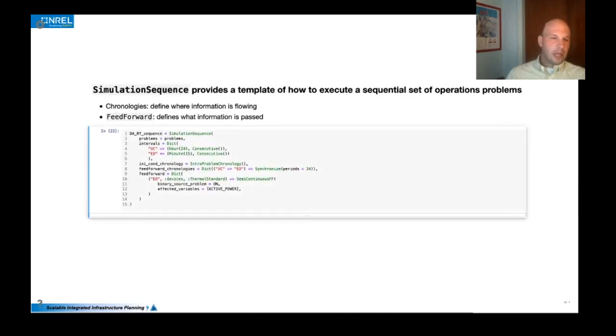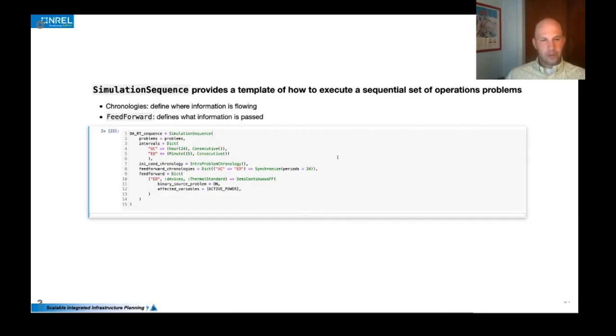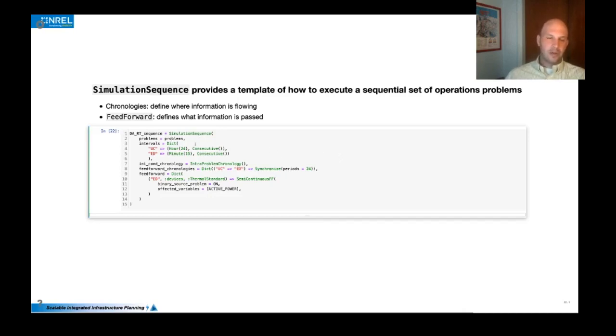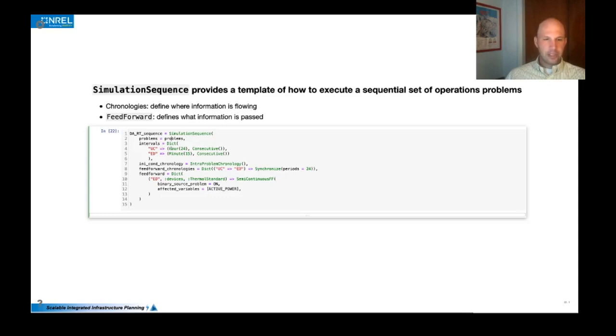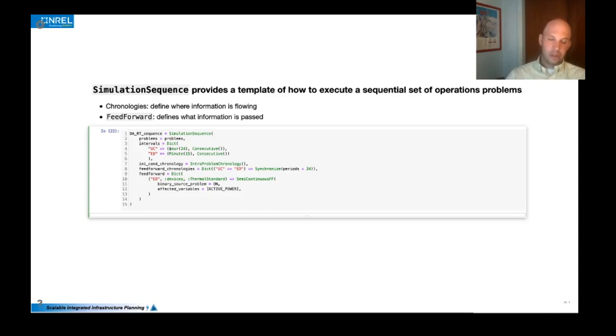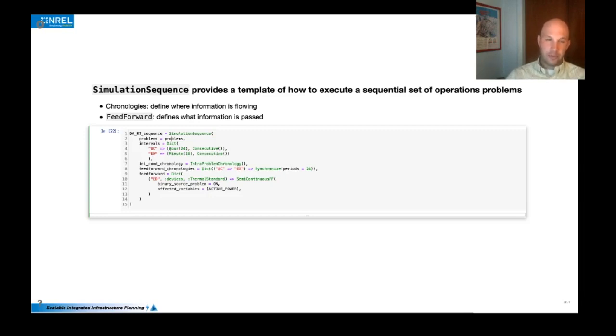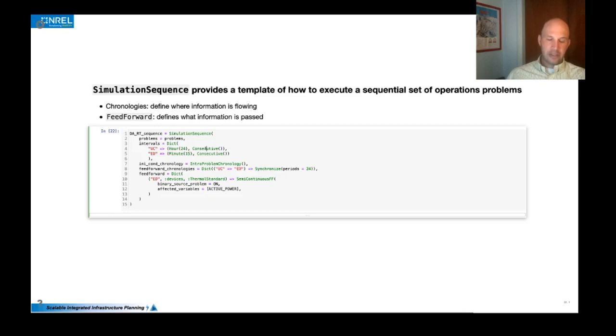And then finally we can also define the way that information flows between those problems and between different steps of those problems. And so we call this a sequence and the sequence really takes that list of problems and then it defines a few things. So first it defines the horizon of the problem. And in the unit commitment case, we have a 48 hour problem, but each time we solve that problem, we want to step forward 24 hours and that's this interval calculation here. And we want to do that in a consecutive fashion. We have other options of receding horizon and things like that. Similarly with the economic dispatch, we want to solve one hour problems stepping forward 15 minutes each time.